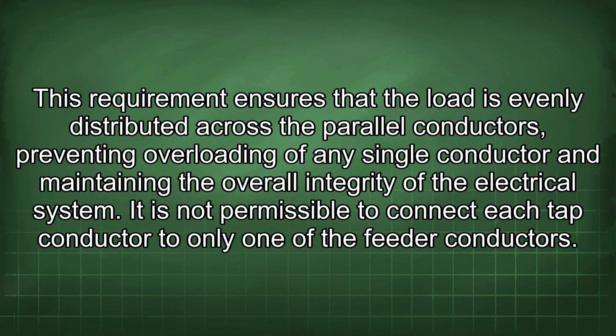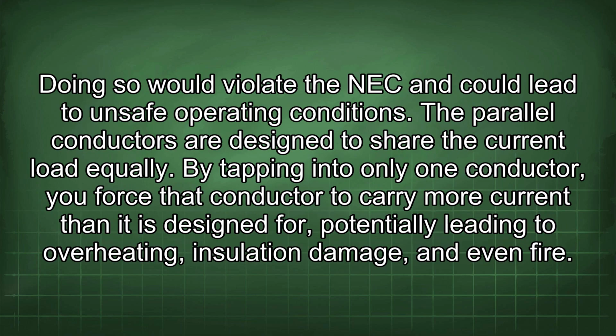This requirement ensures that the load is evenly distributed across the parallel conductors, preventing overloading of any single conductor and maintaining the overall integrity of the electrical system. It is not permissible to connect each tap conductor to only one of the feeder conductors. Doing so would violate the NEC and could lead to unsafe operating conditions. The parallel conductors are designed to share the current load equally. By tapping into only one conductor, you force that conductor to carry more current than it is designed for, potentially leading to overheating, insulation damage, and even fire.